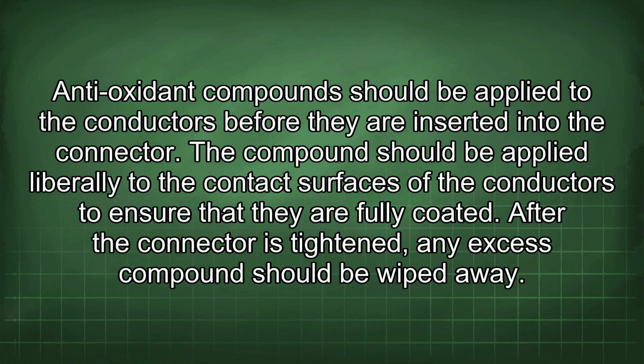Antioxidant compounds should be applied to the conductors before they are inserted into the connector. The compound should be applied liberally to the contact surfaces of the conductors to ensure that they are fully coated. After the connector is tightened, any excess compound should be wiped away.